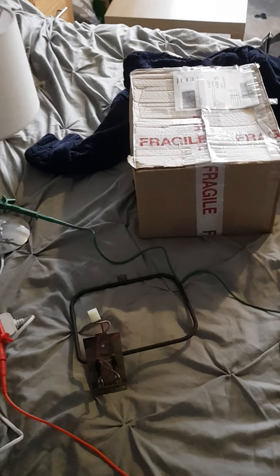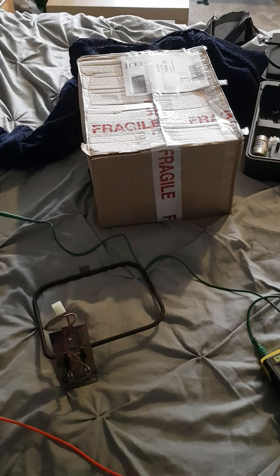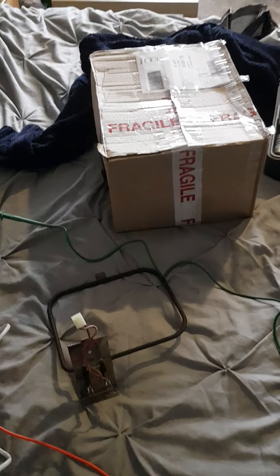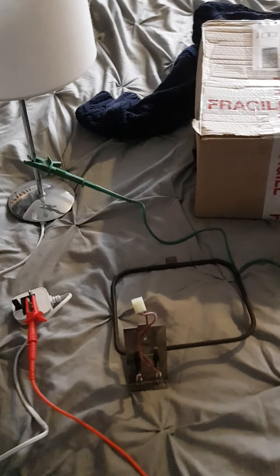Before we unbox the new element, we'll demonstrate how the Megger tester works. This tester tells you if things are safely insulated. Electric elements like this should have no continuity between the actual element and either of the connections on them.